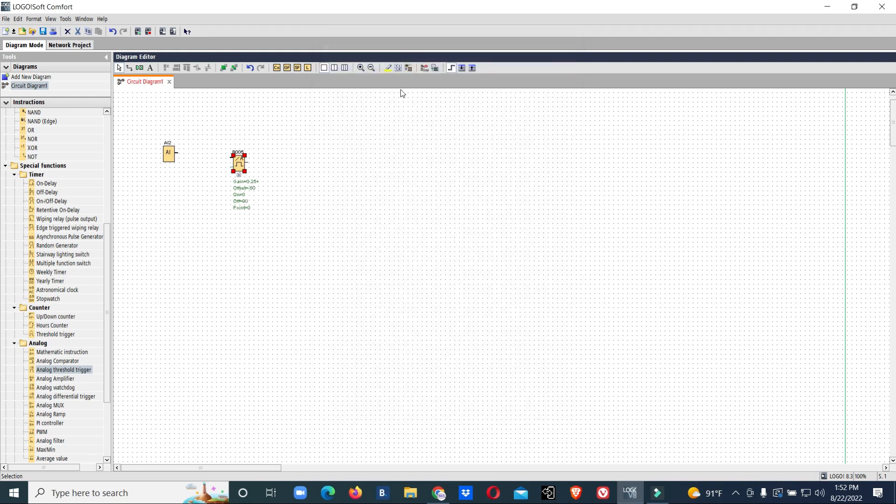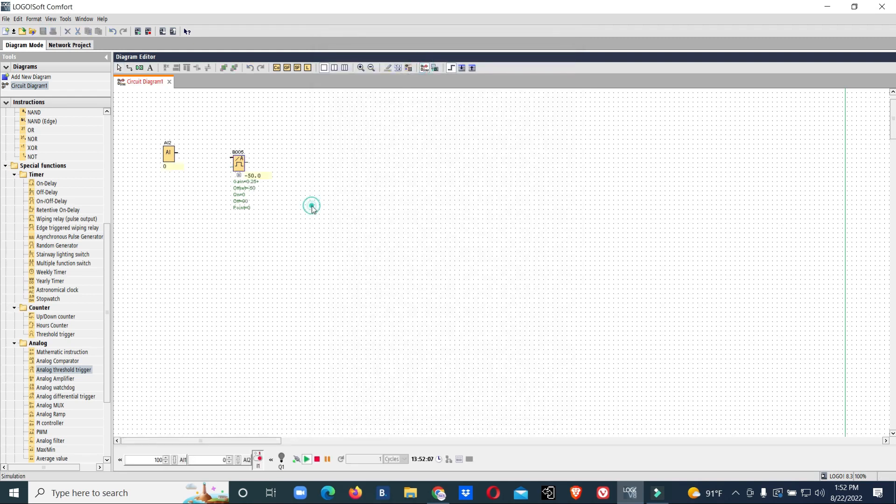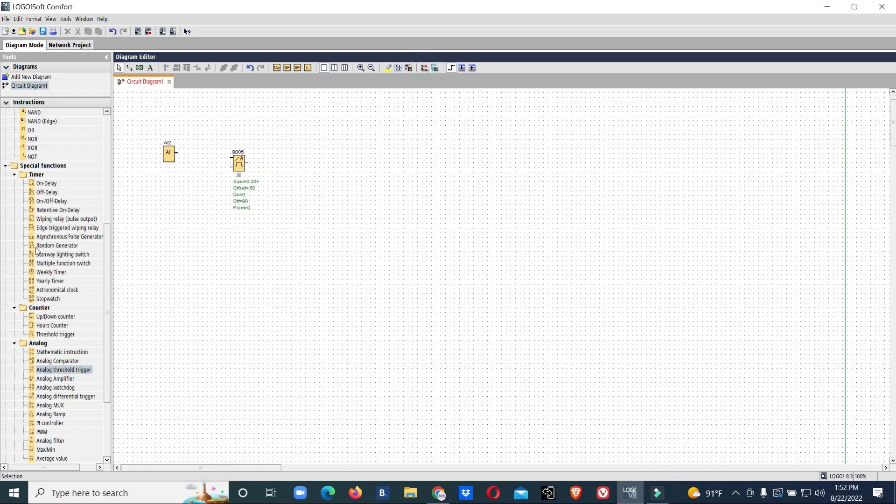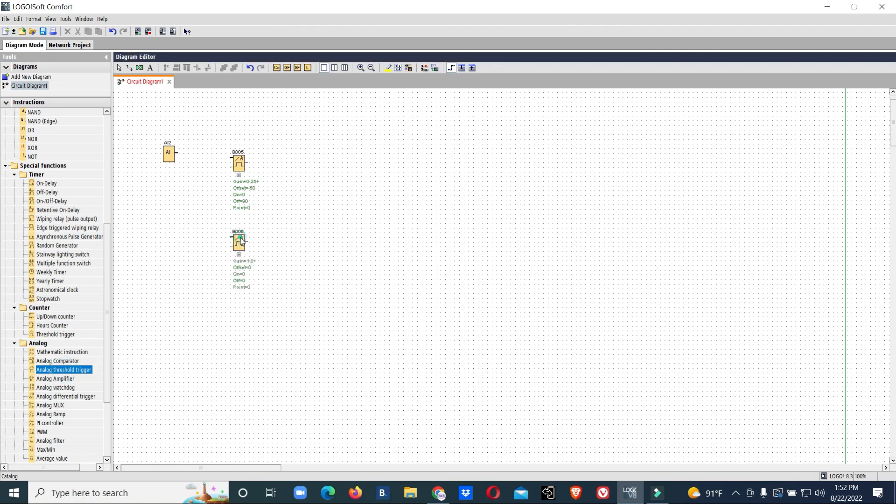We will go for zero and 90. 90 is our cutoff range. Then we will go for cut-in. From 80 it should start, at 90 it should cut off.